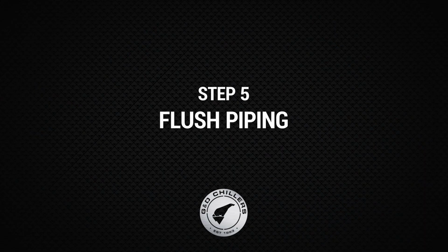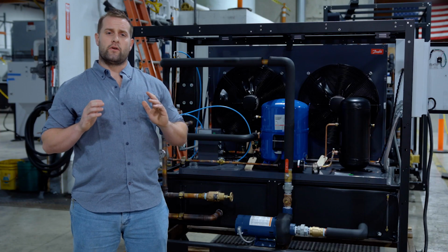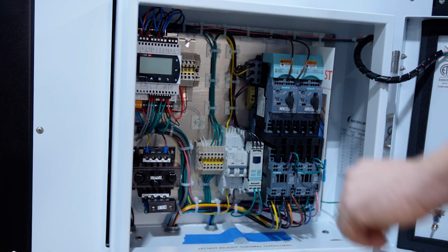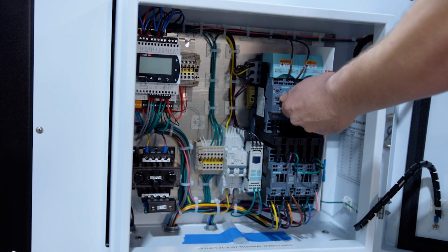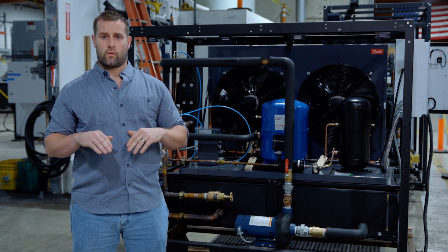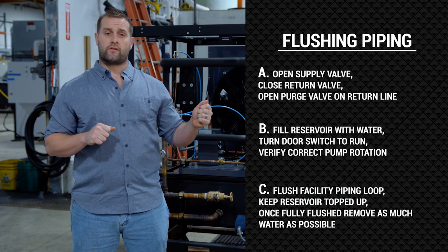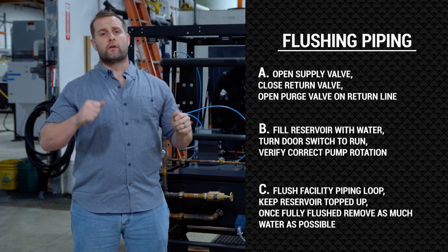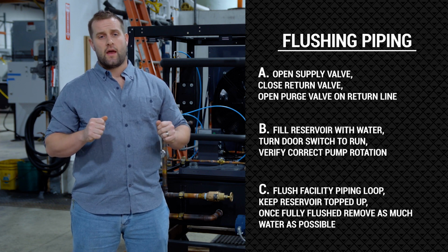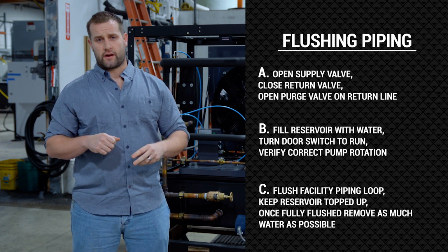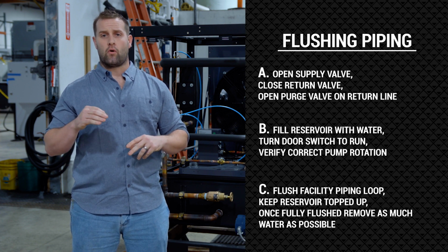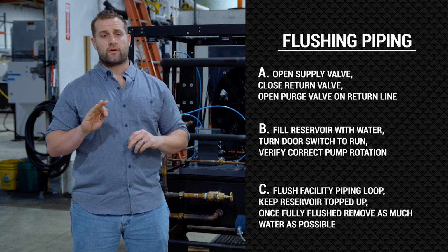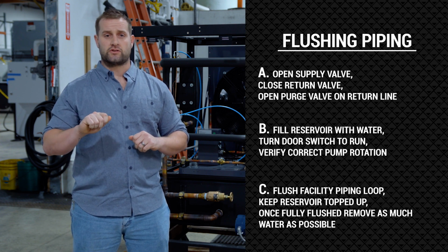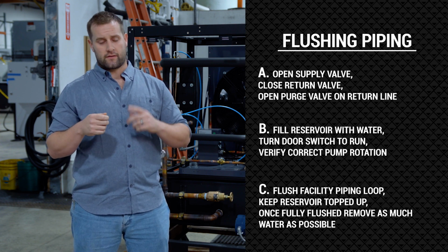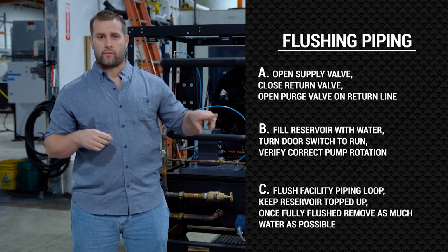The next step of the startup is flushing your process piping. You're going to ensure that the compressor breakers are shut off in the panel, and you're going to fill your reservoir with water. You're going to open your supply valve to your process piping, close your return valve at the chiller, and you're going to be filtering water out the Y strainer. Once you have the reservoir full, again making sure that your compressor breakers are off, you're going to turn the door switch on and allow the pump to run, and it's going to start flushing water throughout your process piping.